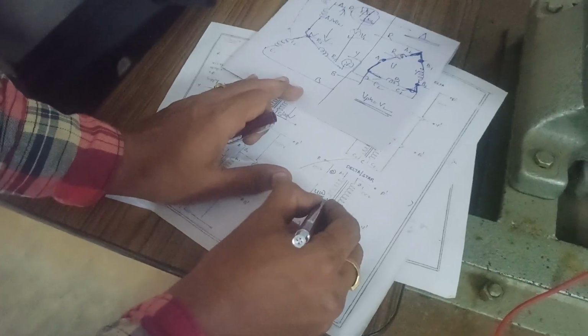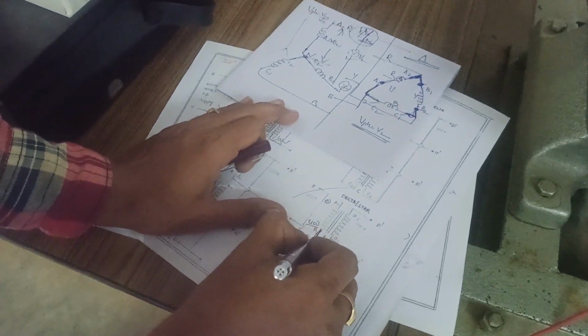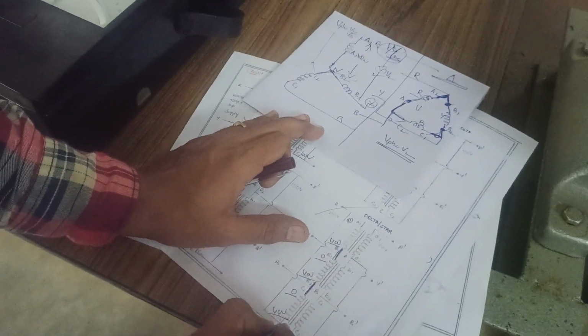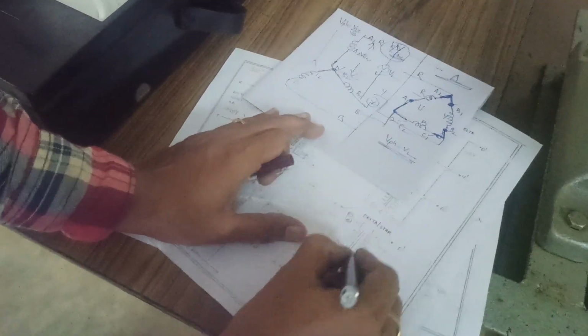The windings are marked 0-400, 0-400, 0-400. As already explained, to connect in delta you join A2-B1, meaning join 400 and 0, join 400 and 0, join 400 and 0, and automatically it gets connected at 0. You can see this connection here.